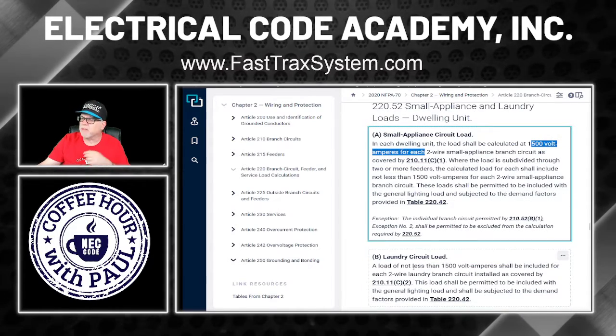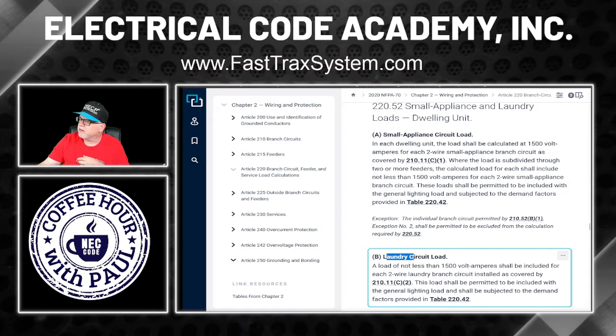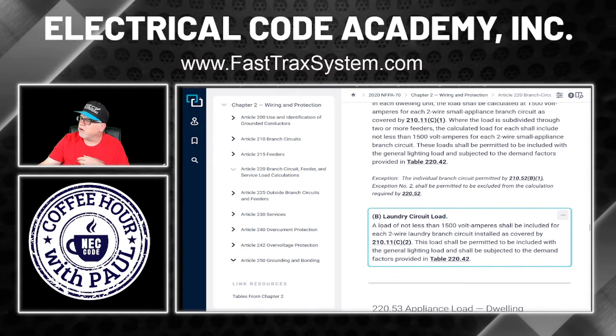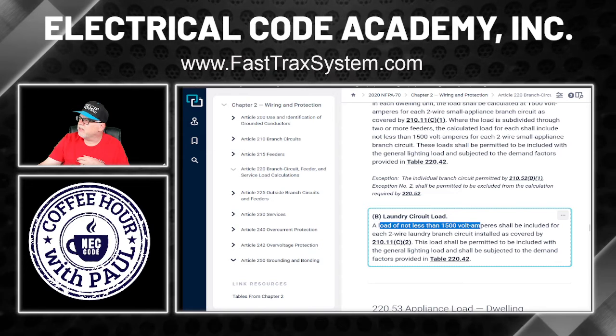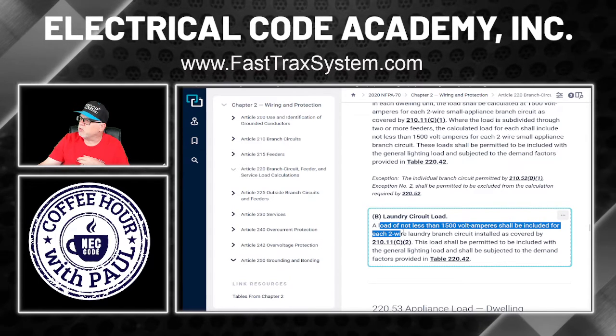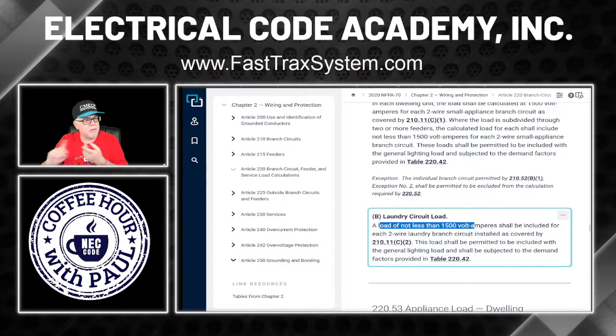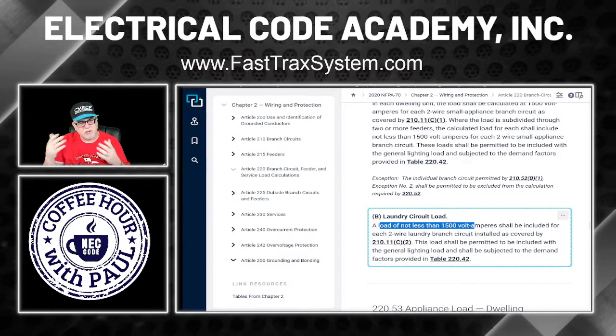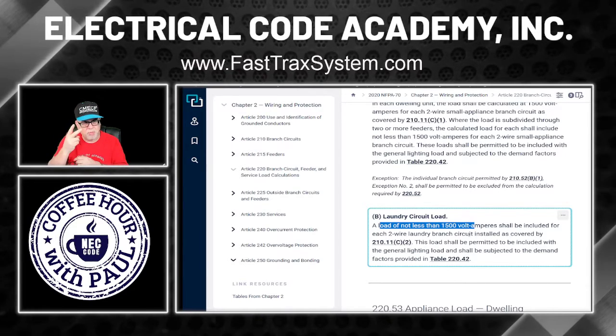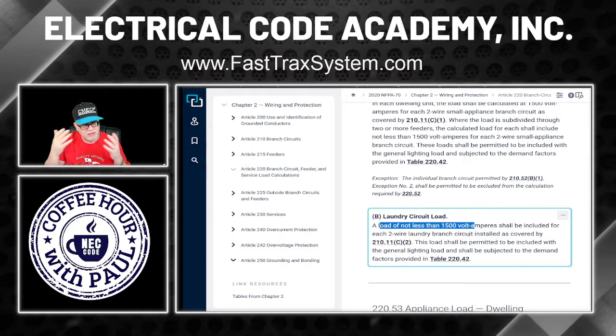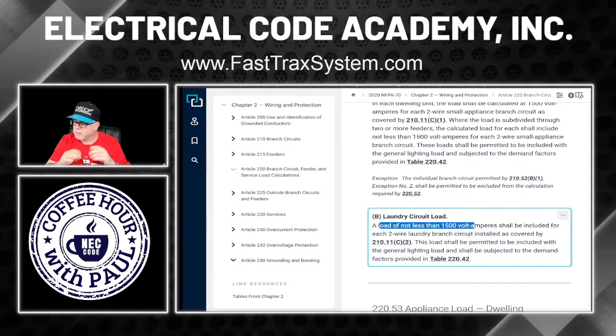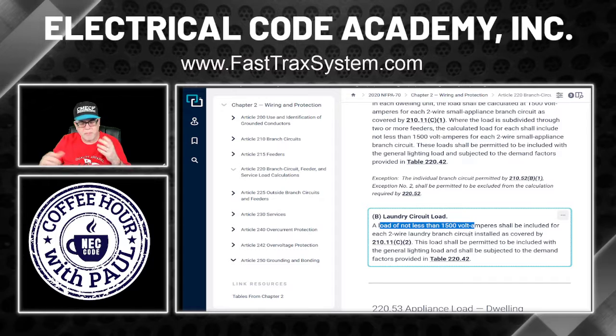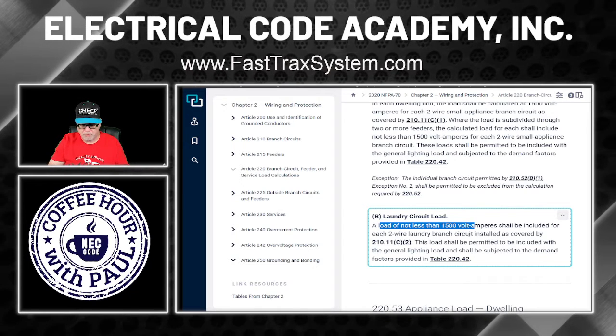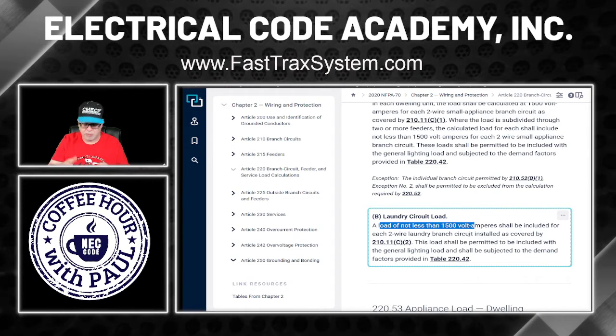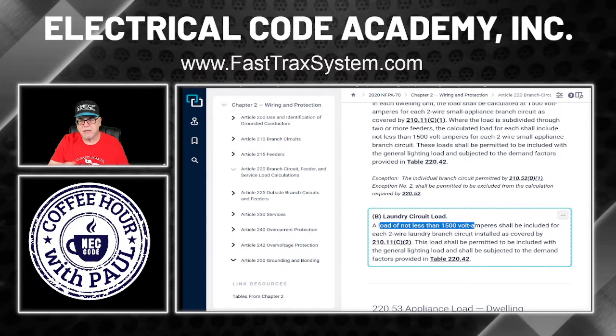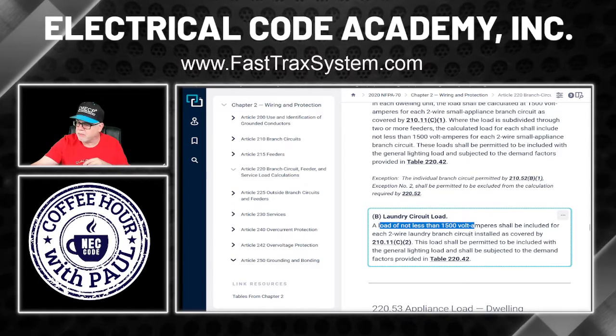And then you go down here. Remember it said for laundry. Here's the laundry. The laundry says a load of not less than 1,500 VA shall be included for each 2-wire laundry branch circuit. And remember, if you install more than 2, that's 1,500 each. Same with the small appliance. 2 minimum. If you put 3 in, it's 1,500 times 3. Remember that now. So in this case, it's just the bare minimum. So we had 1,500. Since they're all 1,500, we can just do 1,500 times 3. And that's 4,500. Okay, so let's come back to the question.